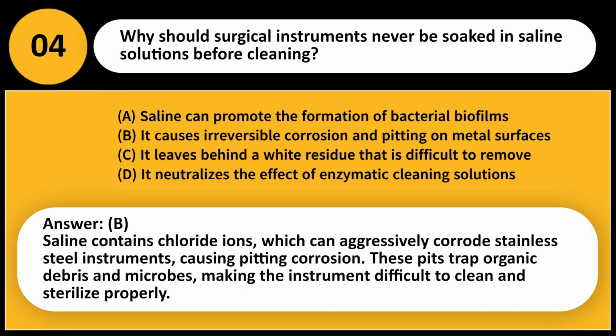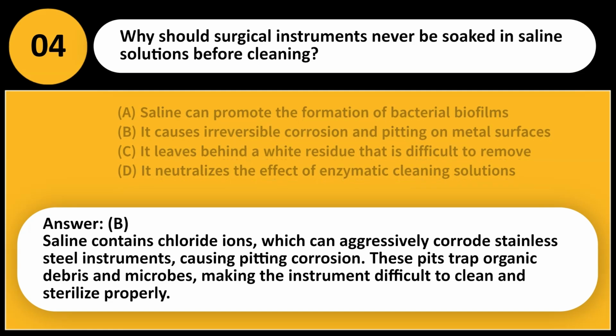Answer, B. Saline contains chloride ions, which can aggressively corrode stainless steel instruments, causing pitting corrosion. These pits trap organic debris and microbes, making the instrument difficult to clean and sterilize properly.